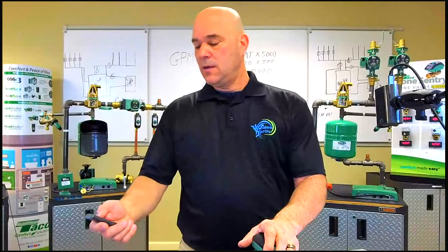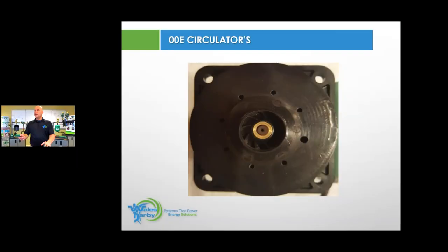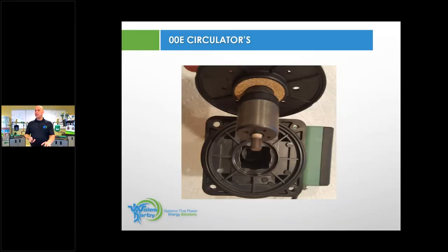So on the circulator here, there's the eye of the circulator. That's what it looks like when we pull it apart. Again, that is the black iron oxide barrier right there. It does not have to be changed. It's not a filter. We always get those questions asked. It's going to stay in the circulator. Normally, when you fill this, it's full. The water stays in the circulator. The only time the water will come out of the circulator is if you drain the system and refill the system, it will refill the cartridge area.